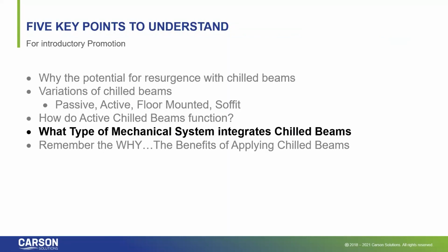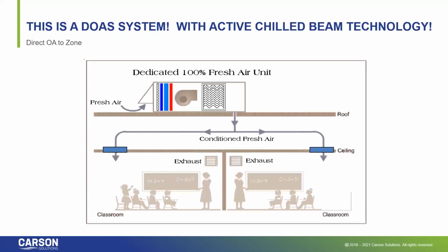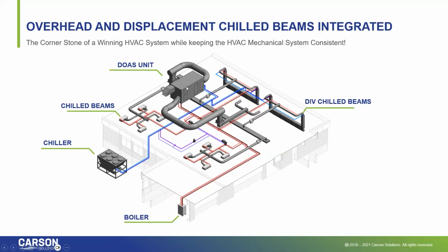So what type of mechanical system typically integrates chill beams? It is a DOAS, or a decoupled system. Here you see on the screen a 100% outside air unit that is either preheating or pre-cooling and dehumidifying that outside air, handling the ventilation load, and more importantly, the latent load of the occupants. And now we have a verifiable, quantifiable amount of outside air that's properly dehumidified to allow the terminal device to be purely sensible.